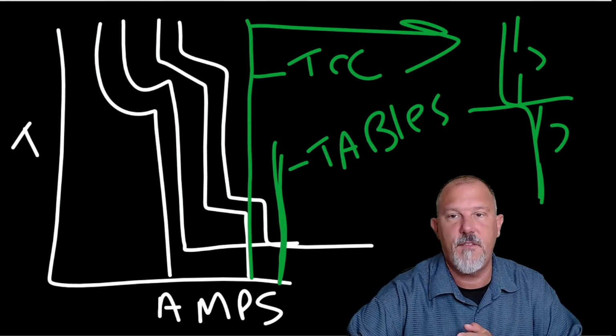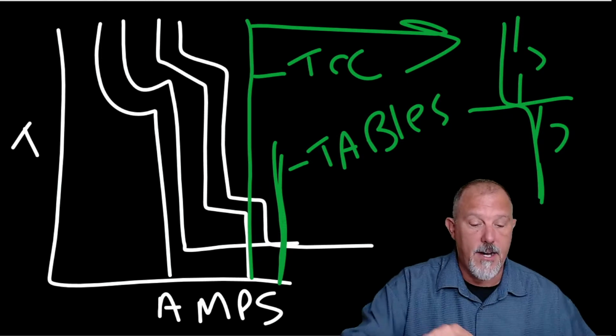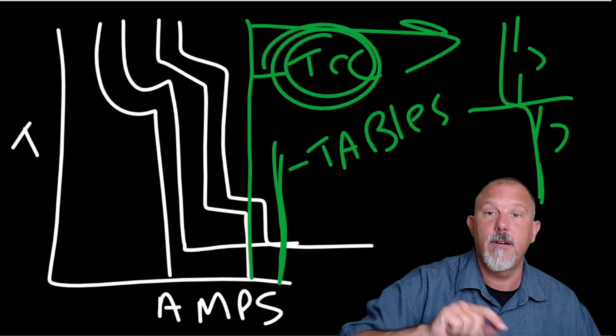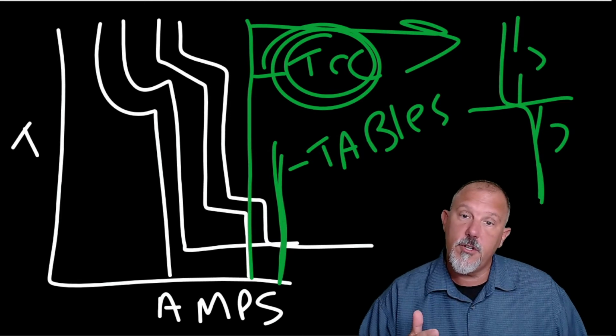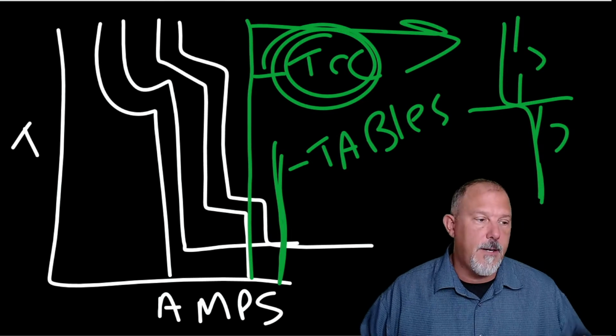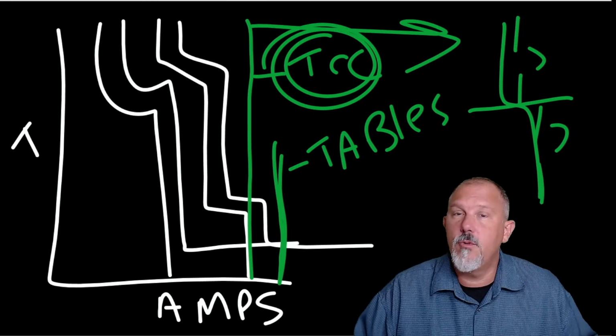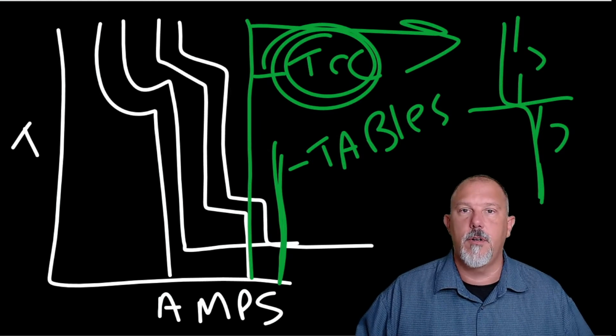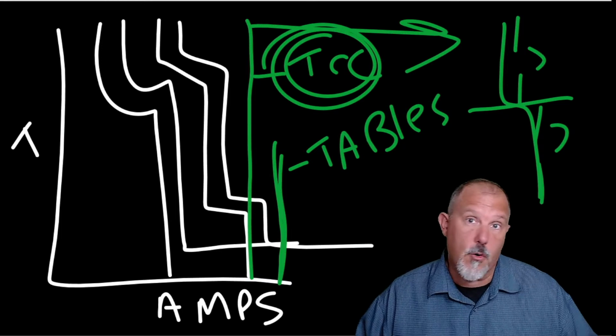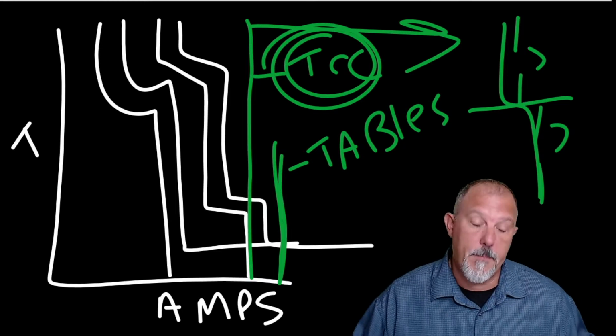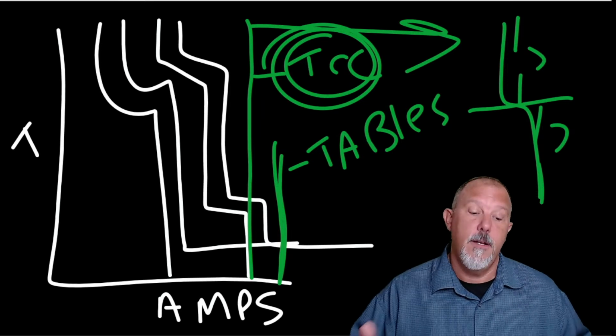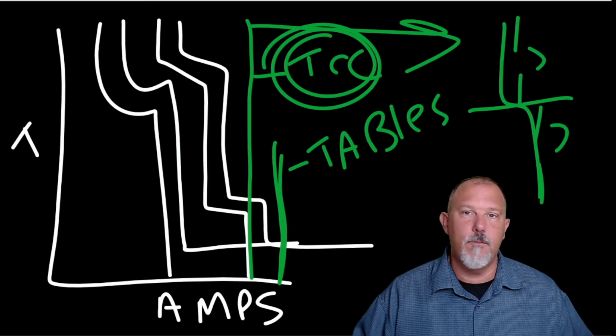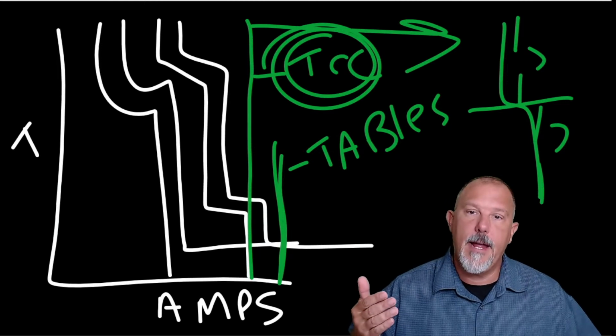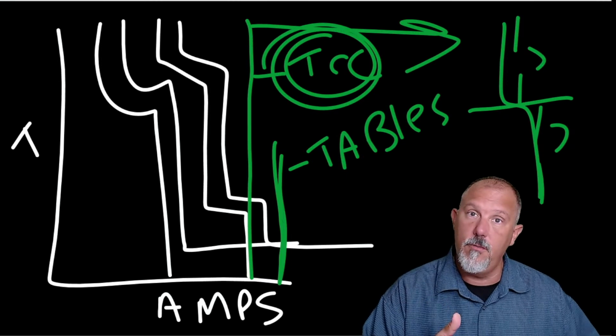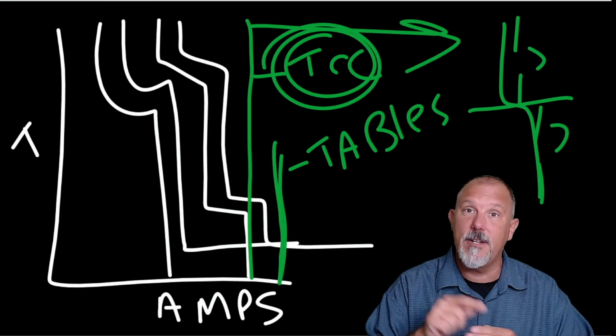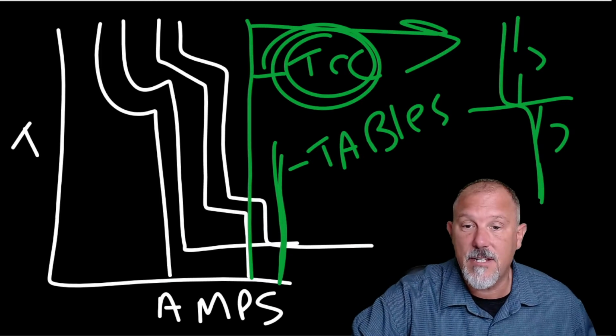If fault current is less than 150 amps, so in that case I'm assuming that 150 amps was this line right here, and the fault current is less than that number, then yes. Like I say, if you want to do an evaluation for ground fault currents and ask which one will open, the ground fault currents might be less. They could be more, but they might be less. You could say, what about an arcing current from an arc flash? They could be less. You just plot your available fault current and look at that fault current in regard to the time current characteristic curves. So that's basically what's going on there.